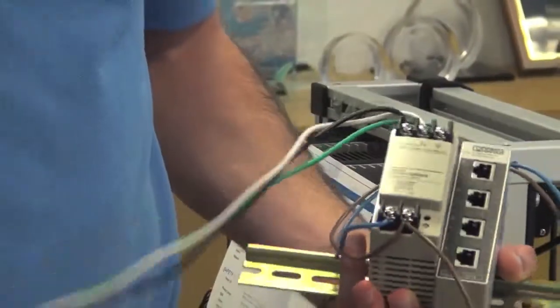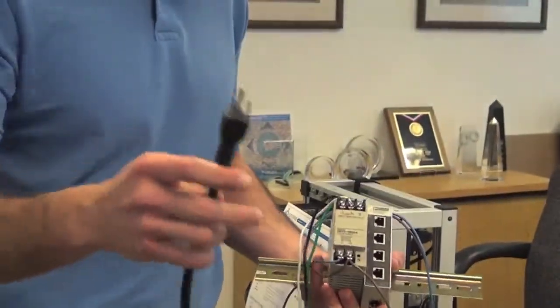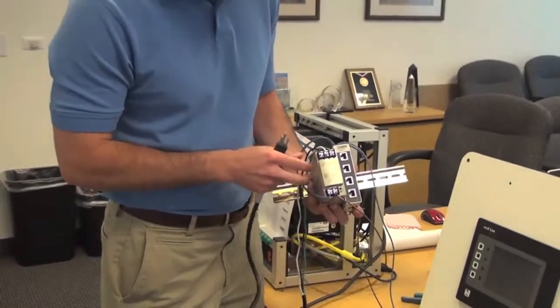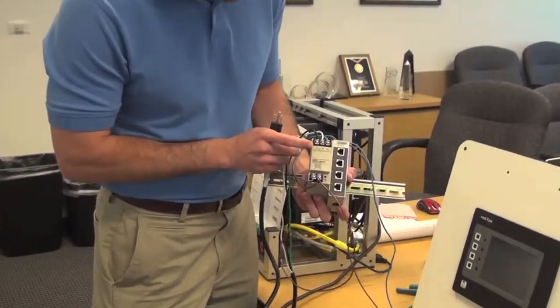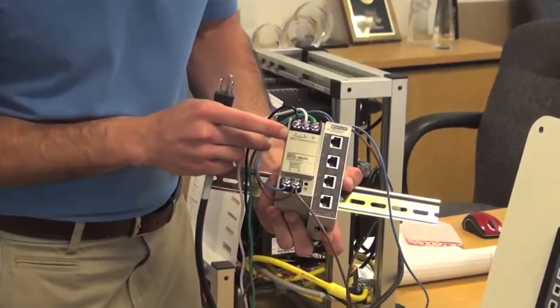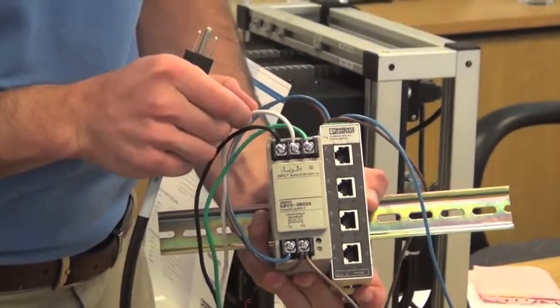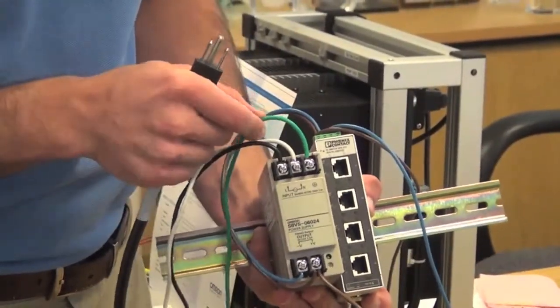We'll take a 120 volts AC cable and land the leads to the Omron power supply. Black goes to L, white goes to neutral or N, green goes to ground.